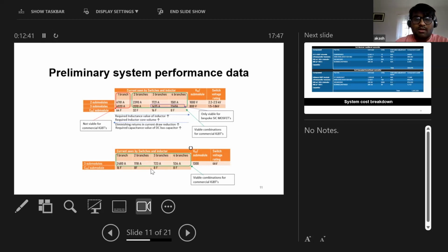Same thing goes for the multi-level converter. The main difference you notice here is because of the much higher branch or submodule voltage, you'll see reduced currents within the branch, but each submodule is going to see the entire current within the branch, and the switch voltage rating also has to go up. But this is a more viable combination for commercial IGBTs, because usually when you have high current ratings, you also have high voltage ratings, but you don't have the opposite, where you have low voltage ratings and high current ratings.